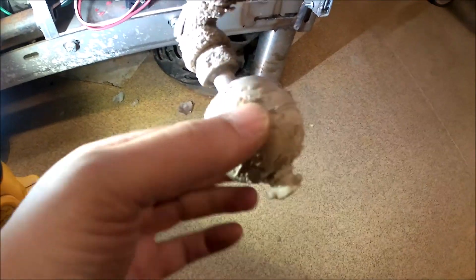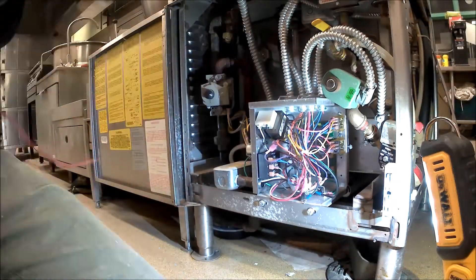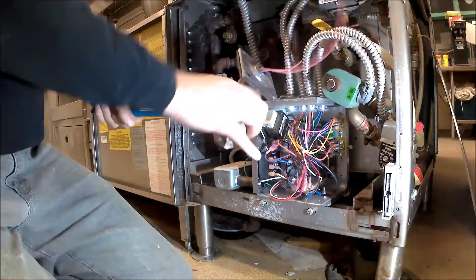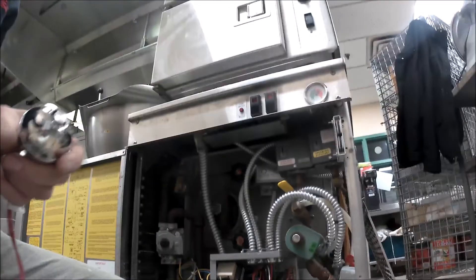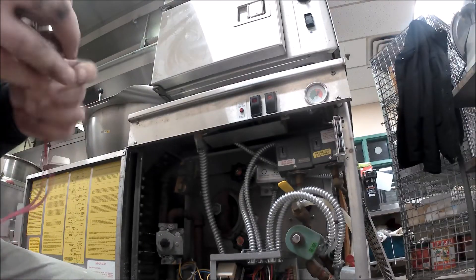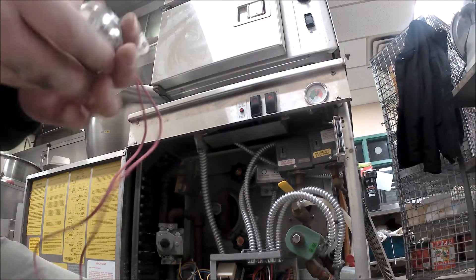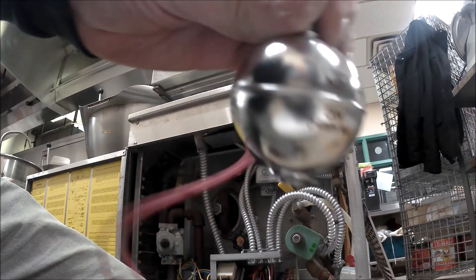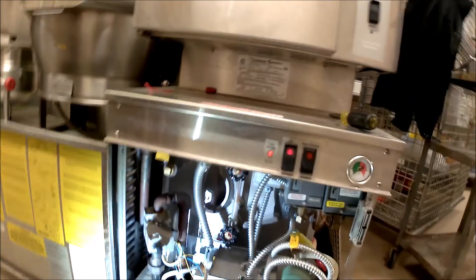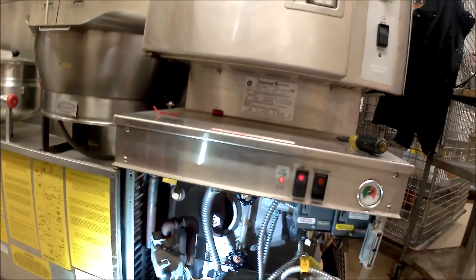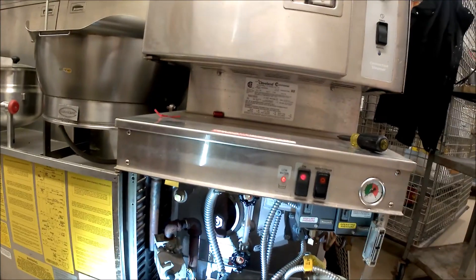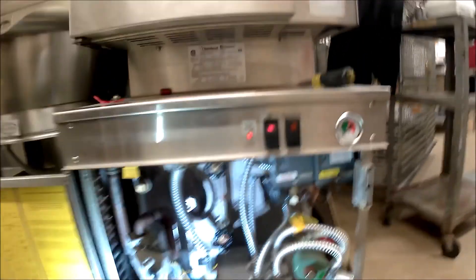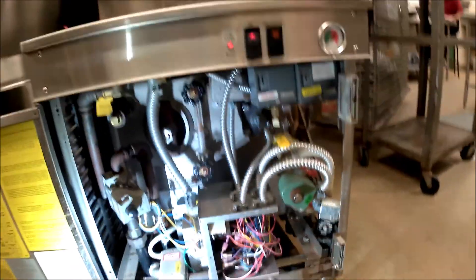I do have a new one. You can see it scaled up pretty badly. In there you can see the high and low probes. I'm going to go ahead and clean these while I got the chance right now. Get everything cleaned up, the boiler is actually in good condition now. The new float switch - if it comes upside down it'll not work. There's a normally open and normally closed, so you want to make sure you test that, make sure it's working as it should.